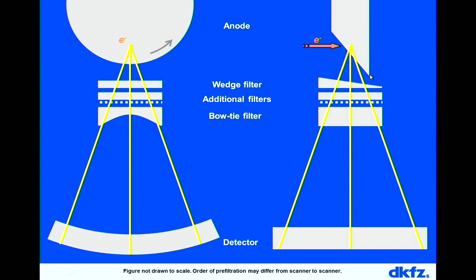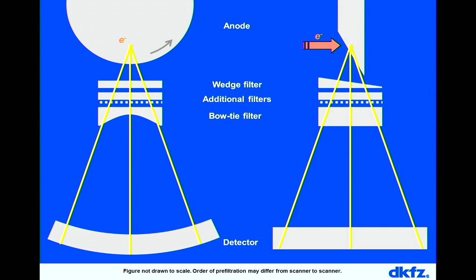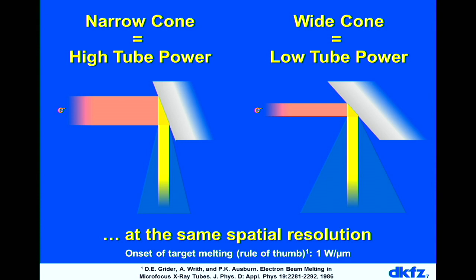CT systems differ in detector size. A very large detector requires a larger anode angle. The difference is that the electron beam must be narrower when hitting a large-angle anode, while the beam can be much thicker for a small-angle anode, allowing more tube power. There is no difference in spatial resolution because the patient sees the X-ray tube from below. The narrow cone beam allows high tube power; the wide cone beam — with 256 or 320 detector rows — does not allow such high tube powers.